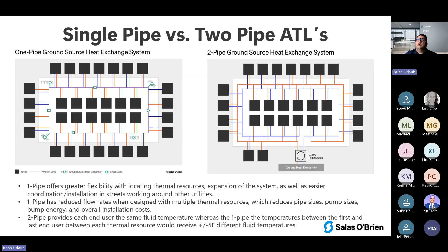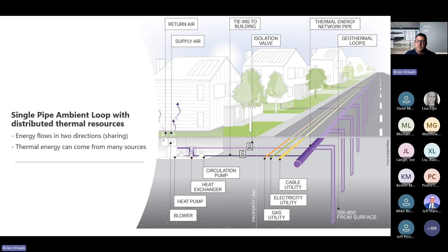And again, the great thing about this is that energy flows in both directions. Whereas if you were doing like a hot water, chilled water, generally your energy is going to one direction. And then depending on your central plant, if you've got simultaneous equipment that can take advantage of that, now you can do that. But if you're using a boiler and a chiller, you're not really able to do a lot of simultaneous. So unless you're using heat pumps and can take advantage of that, this is a great way to share energy, especially when you're doing heating and cooling at the same time.